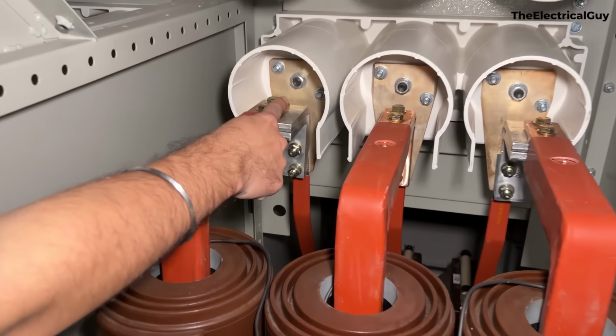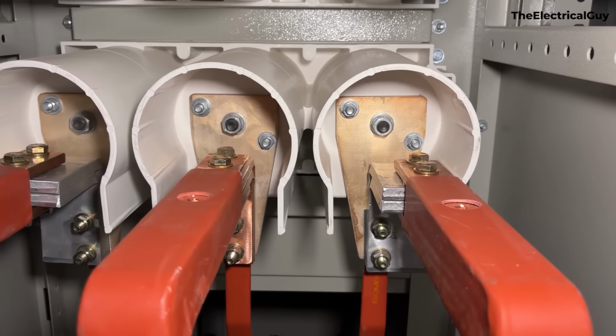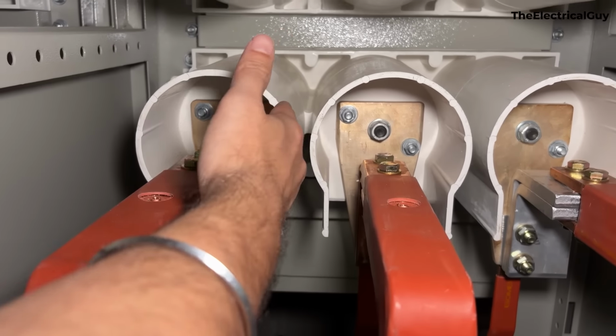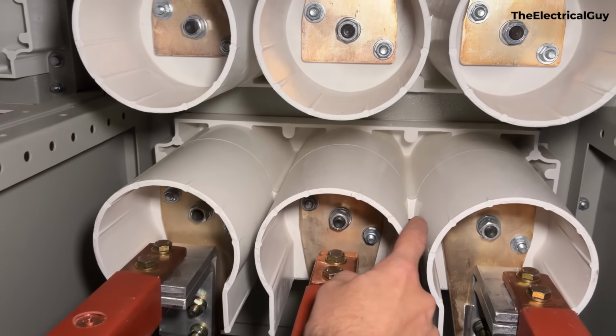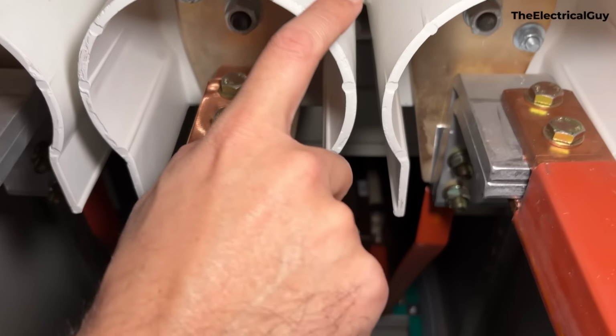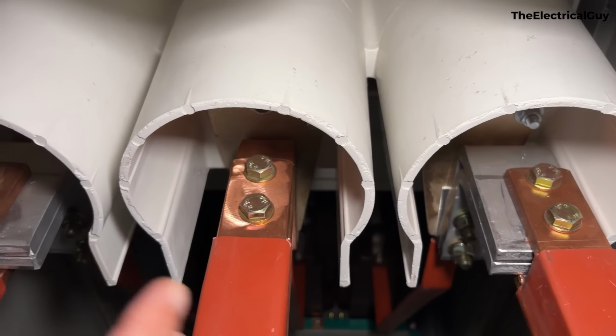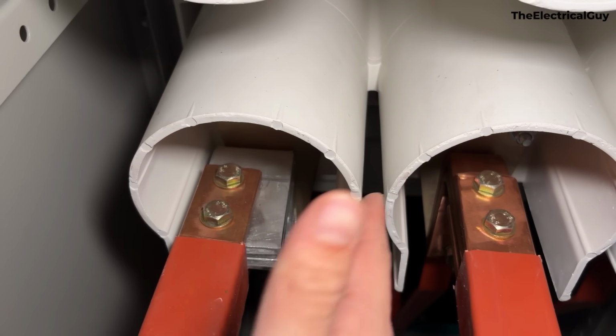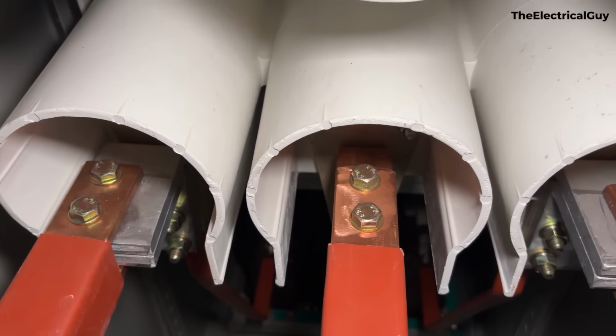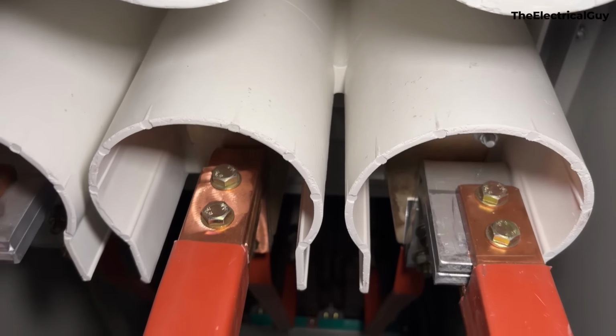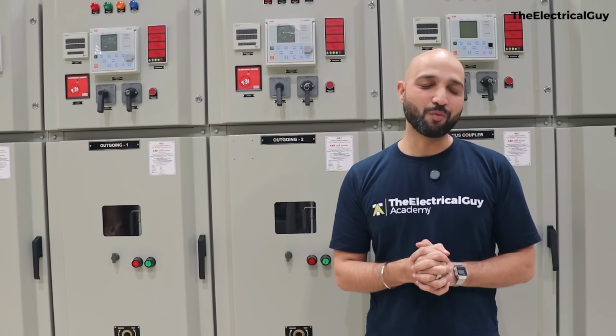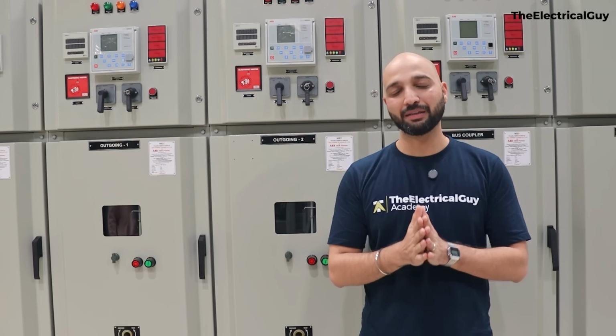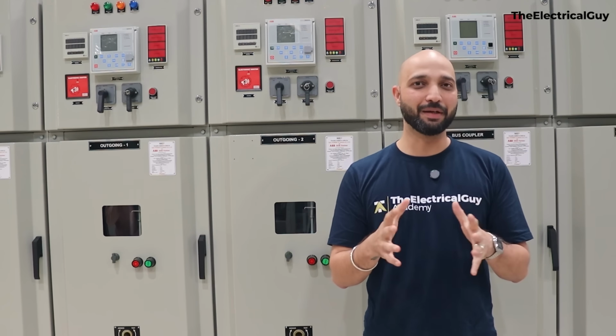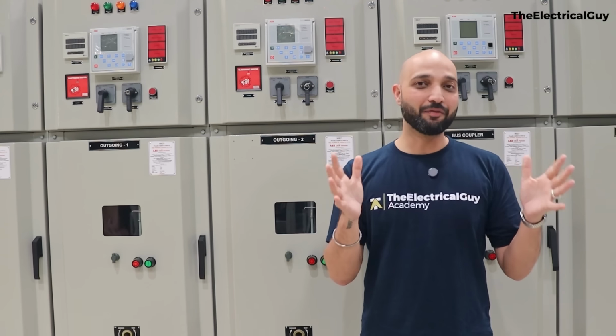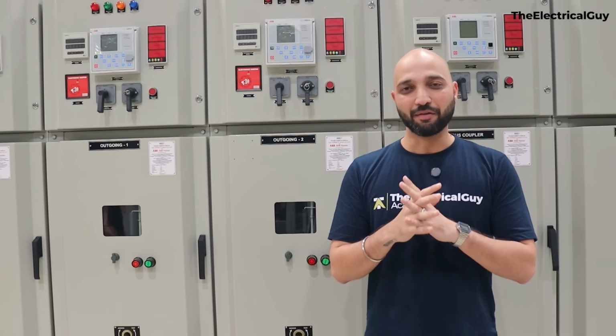Now we also have a vacuum circuit breaker there, which you can see the terminals. Now inside that, of course, vacuum is the insulation, but between the phases, even this part here, it is with air, and that's why it's called as the air insulated switchgear. If it had been a GIS, then we would be using insulating gas which is not air. So that's the basic difference between AIS and GIS. So we have seen what's inside the panel, what is the function of each panel, the single line diagram of it, and how the equipments are arranged. I hope you understood the different composition of the panels and how they function.